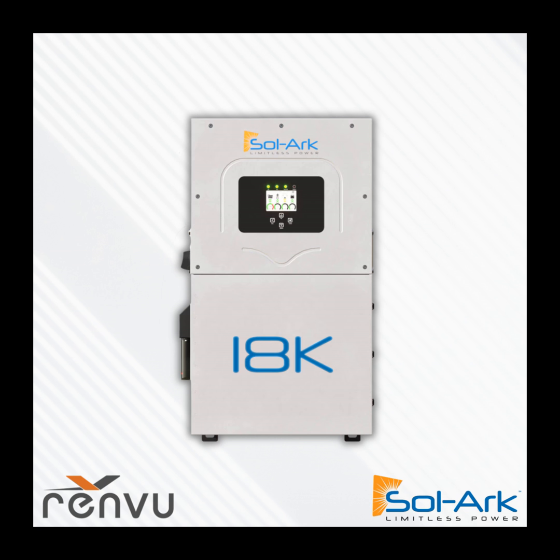Getting into other datasheet items, it's stackable to 12 units. The DC charger has gone from 275 amps to 350 amps on the battery side. And that's where, if you see another inverter that's claiming it's larger than the Sol-Ark, go into the data sheet and look at the amperage ratings, because I saw a 24 kilowatt inverter at RE Plus and its DC charger was 290 amps. I don't know about that inverter, but I know that our inverter can do the 18 kilowatts with battery power. Look at that charging amperage.